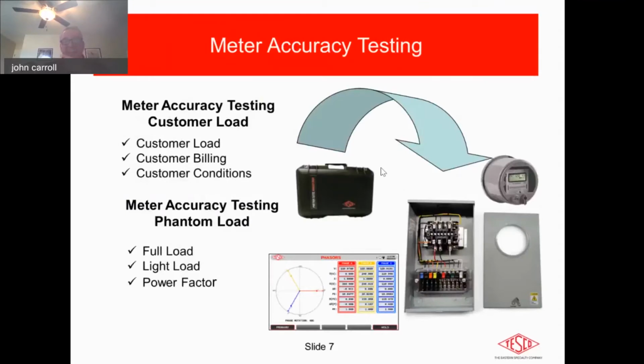So, metering accuracy. Why are we doing this? We're doing this to verify that the meter, when it's installed in service, is performing accurately. It meets its requirements and its classification accuracy, and it meets it under various conditions too. There's a way of testing those meters very easily. You can remove them, as we said, and put them into a test device. We provide a lot of those. You can run the test and the meter comes back 100% and it's fine. But that's not the whole story.